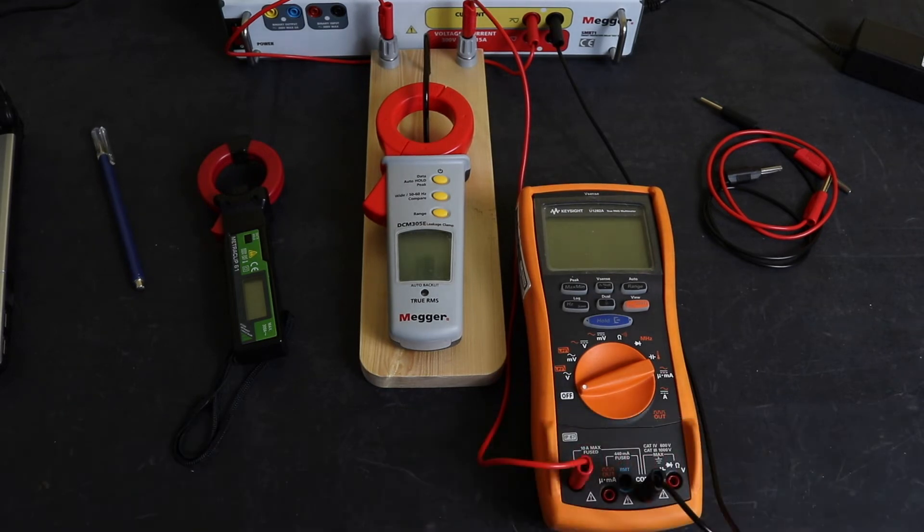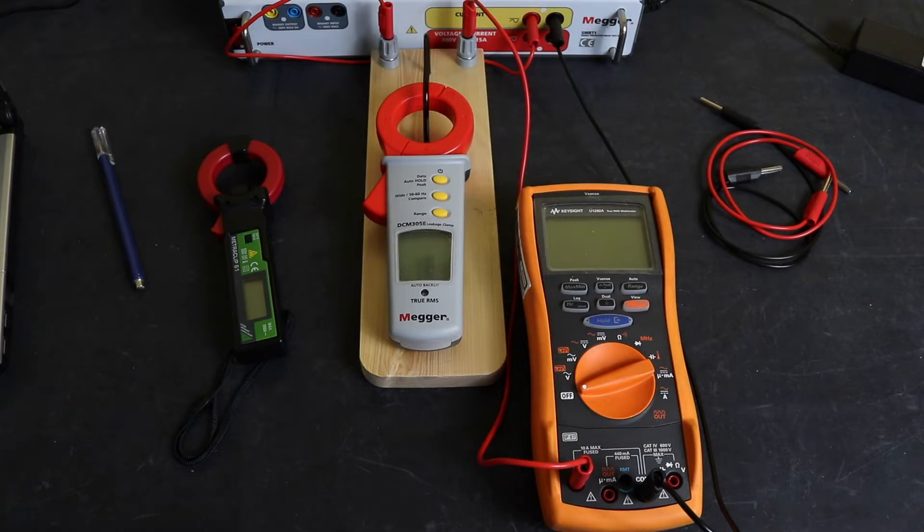Welcome back to the channel, and we are back testing our earth leakage clamps. You've seen my previous video where I tested these out. I had an accuracy issue down at the low range, 1 to 500 milliamps.